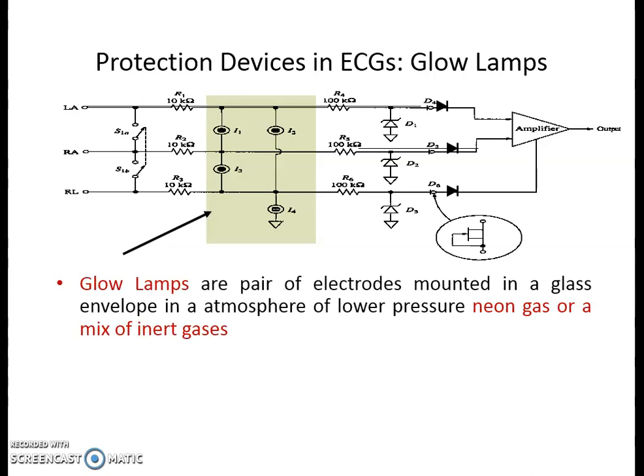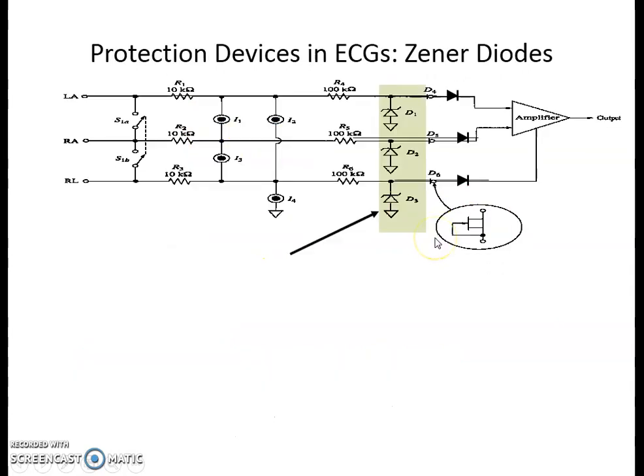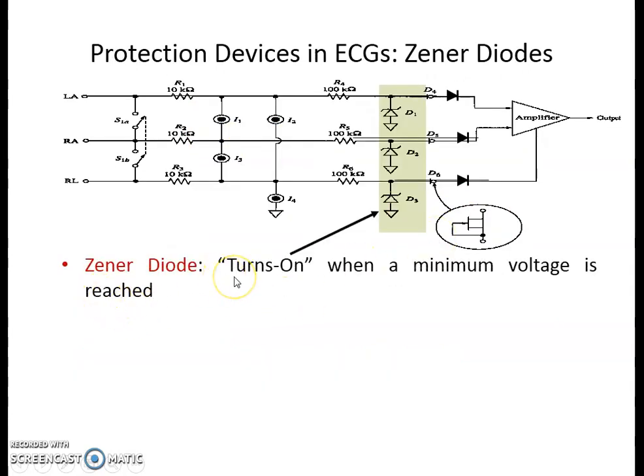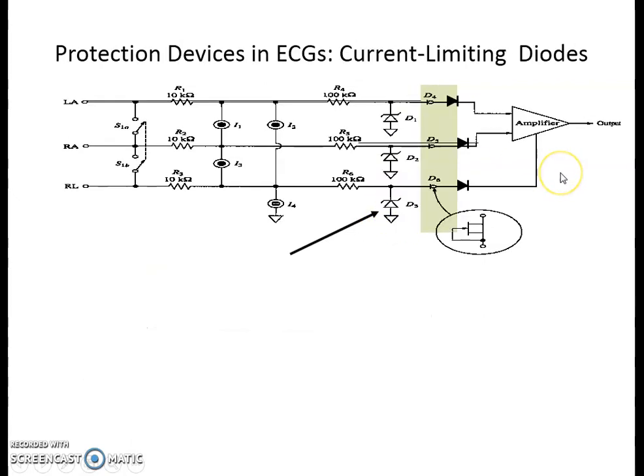The first mechanism is glow lamps — they are generally a pair of electrodes mounted in a glass envelope in an atmosphere of lower pressure neon gas or a mix of inert gases. Typically the impedance across the electrodes is high, but whenever the voltage across the electrodes exceeds the ionization potential of the gas, this impedance suddenly drops and is shorted to ground. So the majority of the current safely goes to ground and avoids the amplifiers. The second mechanism is the Zener diode. These diodes turn on when a minimum voltage is reached, and we use the Zener as a voltage regulator. If a large voltage is applied — as in the case of a defibrillator — the Zener diode allows current to flow through it and shunts it to ground, so current goes to ground and not to the amplifier.